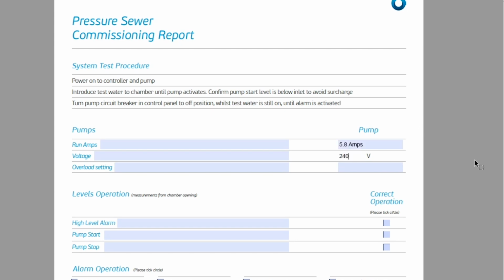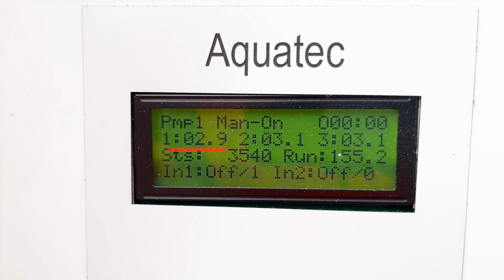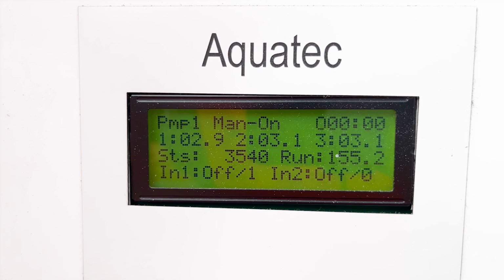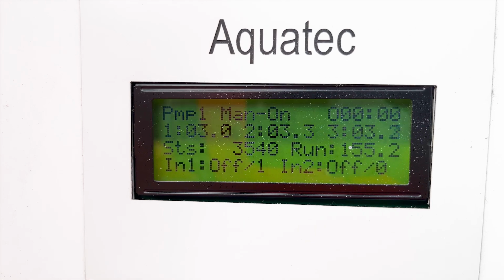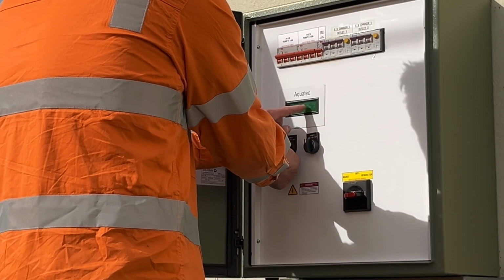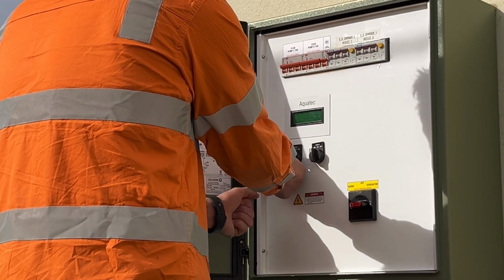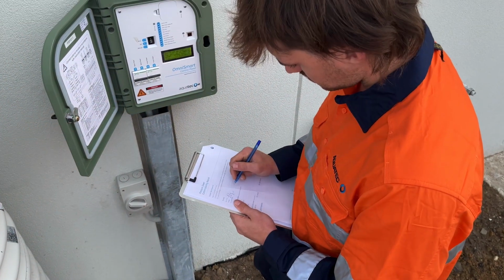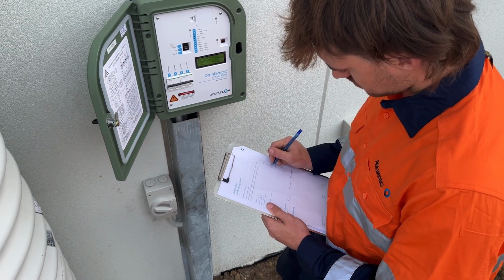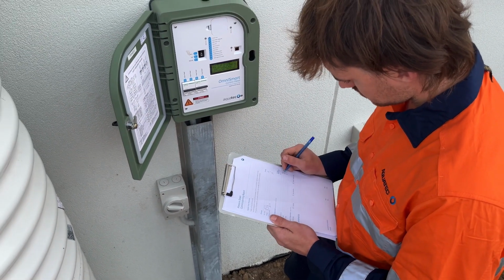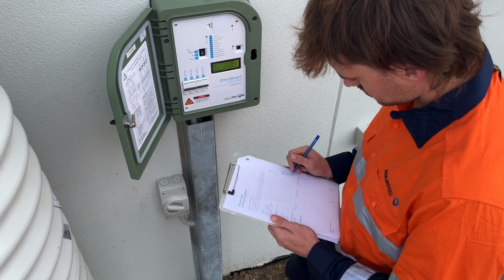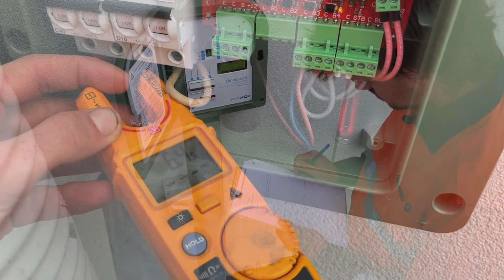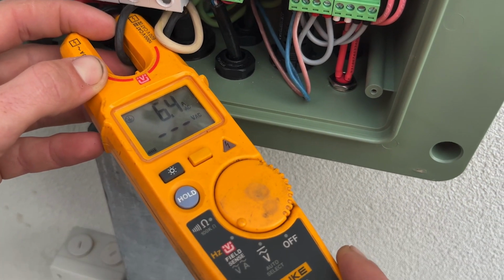There is provision for it in 3-phase and in single phase. In the case of 3-phase, it's important to check the amps for each individual phase of each pump. If there's a discrepancy of between 15 to 20%, that pump should be tagged as requiring further inspection, as it may be malfunctioning. In the case of a single-phase pump, it's just a matter of recording the amps and verifying that they're within spec of the manufacturer's published full load current.